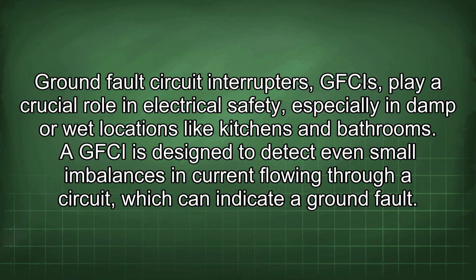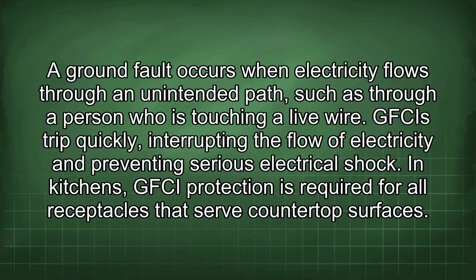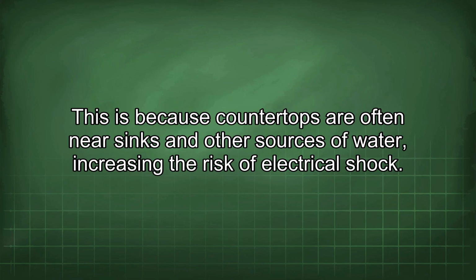Ground fault circuit interrupters, GFCIs, play a crucial role in electrical safety, especially in damp or wet locations like kitchens and bathrooms. A GFCI is designed to detect even small imbalances in current flowing through a circuit, which can indicate a ground fault. A ground fault occurs when electricity flows through an unintended path, such as through a person who is touching a live wire. GFCIs trip quickly, interrupting the flow of electricity and preventing serious electrical shock. In kitchens, GFCI protection is required for all receptacles that serve countertop surfaces. This is because countertops are often near sinks and other sources of water, increasing the risk of electrical shock.